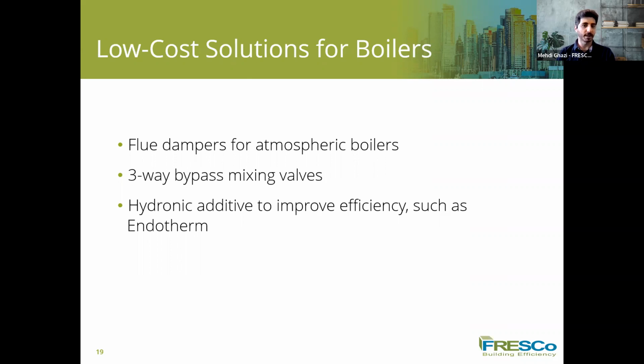Another solution could be hydronic additives. There is a chemical, the brand is Endotherm, and it can be applied easily like an anti-corrosion inhibitor, and it reduces the viscosity of the water, so we will have greater heat transfer, and also in the pumps we can have lower flow friction, so the pumps work in a more efficient condition. This can help us increase the efficiency by 8 to 12% for buildings that don't have a control system, and for buildings that have a condensing boiler with a control system, it can even increase the efficiency by 12 to 15%.